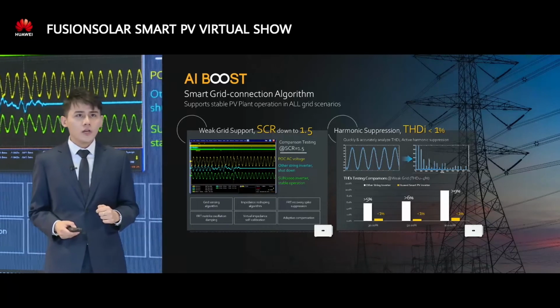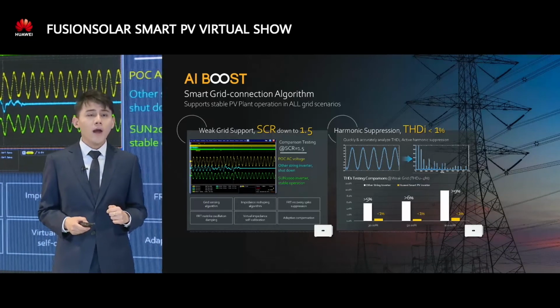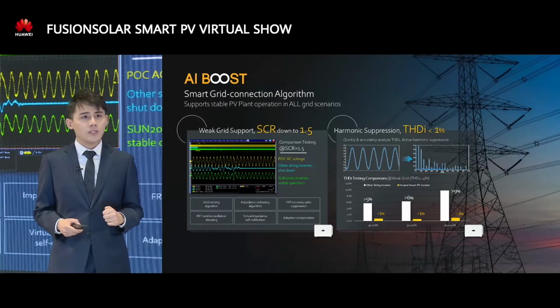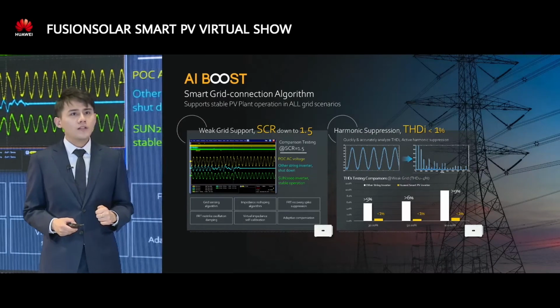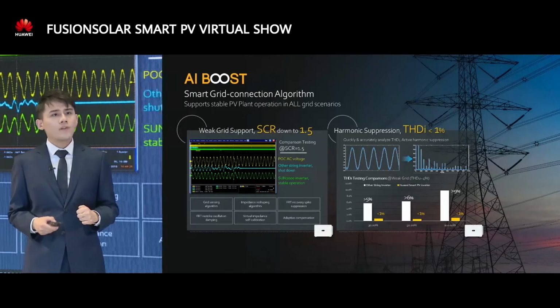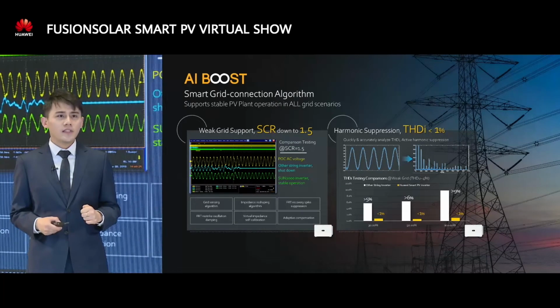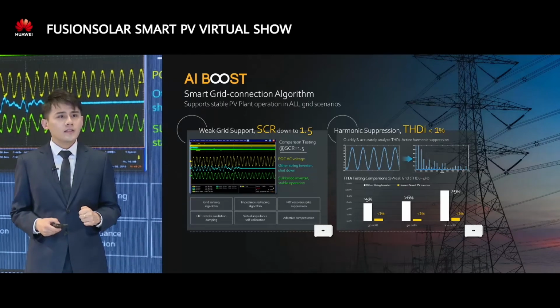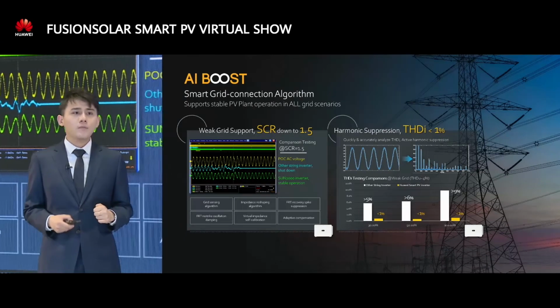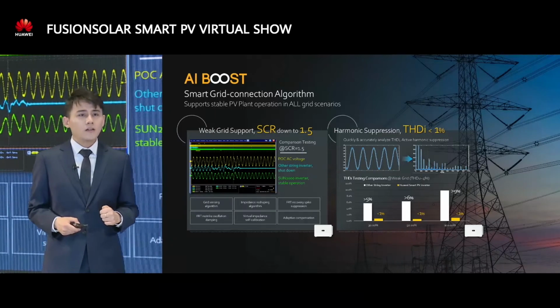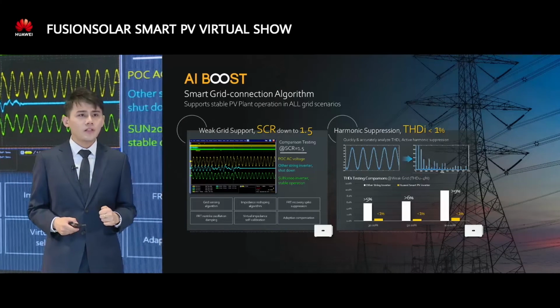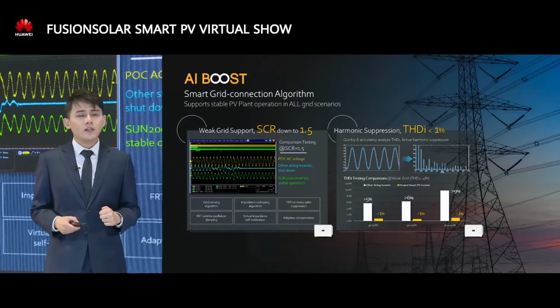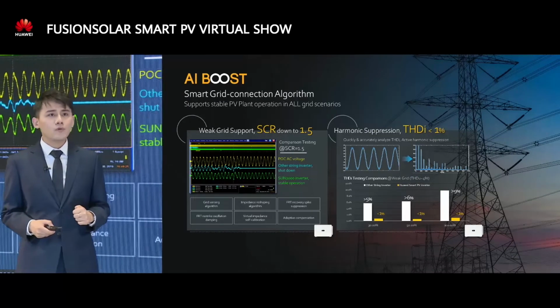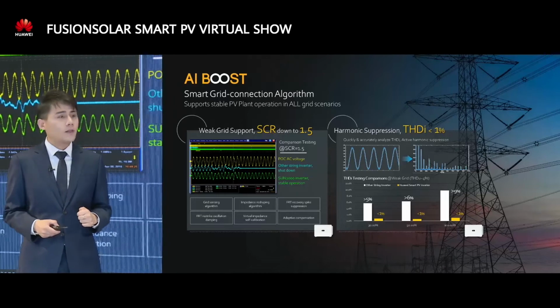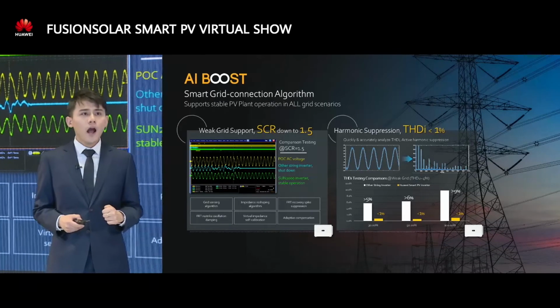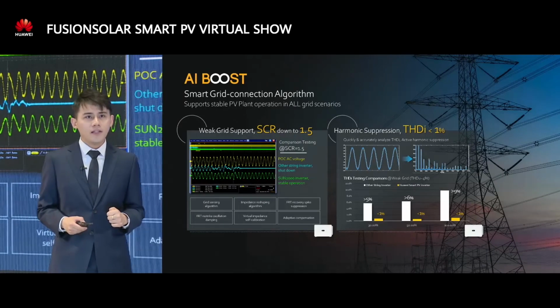Huawei has been researching grid connection PV technology for many years and improving the control accuracy. Currently, Huawei has achieved a stable grid connection in all PV scenarios. The value of this technology for customers is that site selection under the conditions of the changing power grid is not affected. The algorithm supports a stable grid connection in weak power grid with SCR down to 1.5, and improved higher fault ride-through capabilities. At the same time, it improves power quality by suppressing the current harmonics to less than 1%.